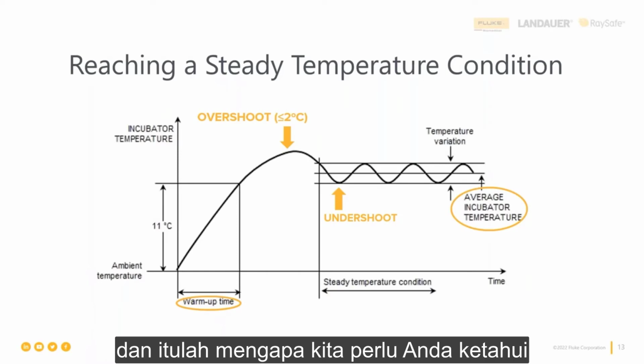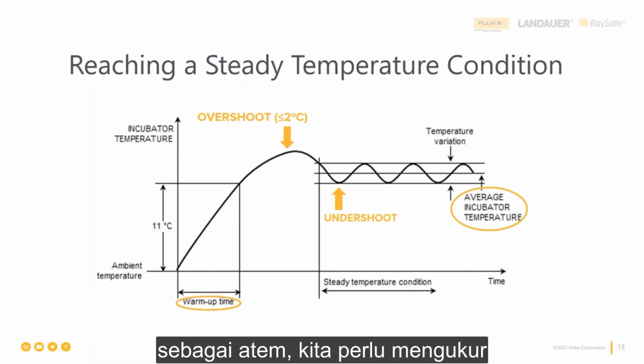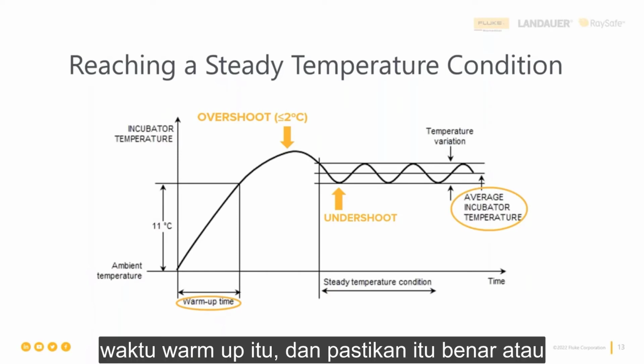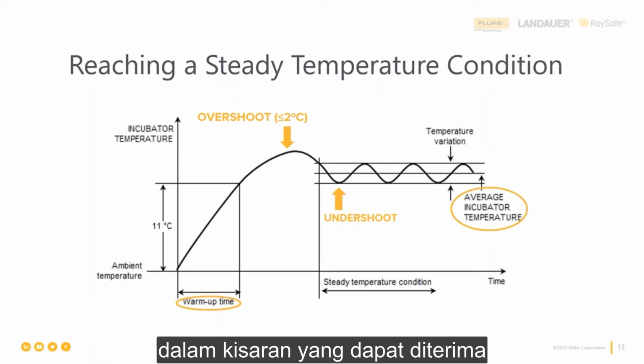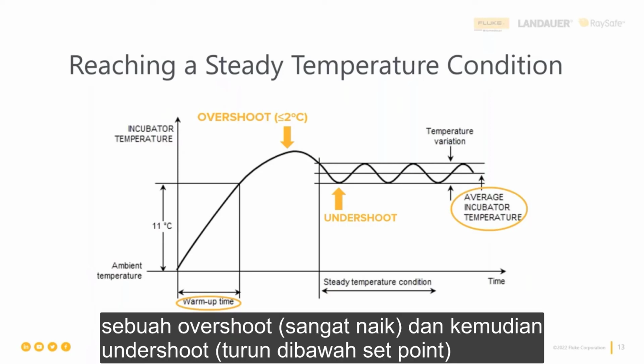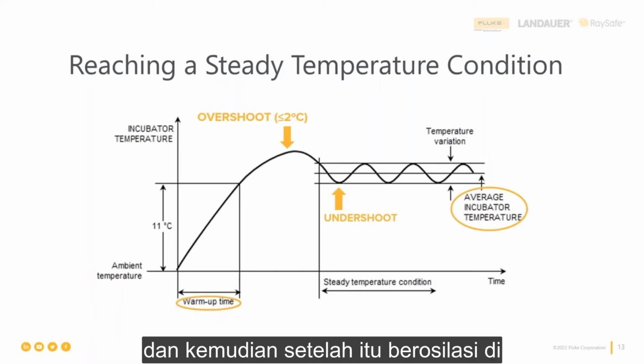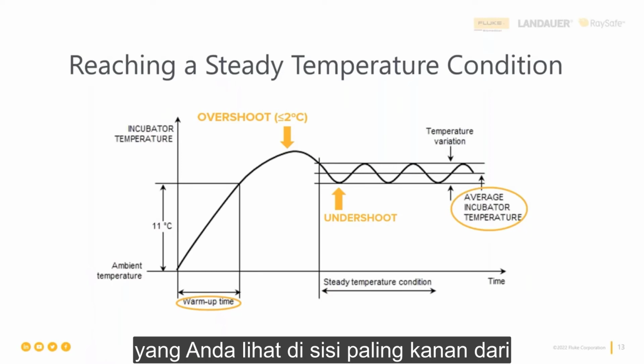And that is why we need to, as biomeds, measure that warm-up time and make sure that it is correct or within the acceptable range. So after the incubator goes through its warm-up time and reaches its set point, it actually goes into overshoot and then undershoot. And then after that, it oscillates in small temperature variations, resulting in an average incubator temperature that you see at the very right side of the slide.